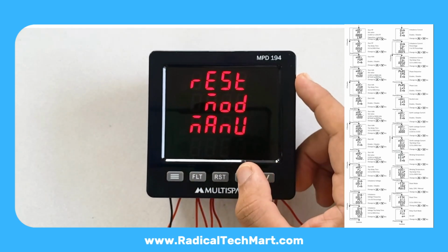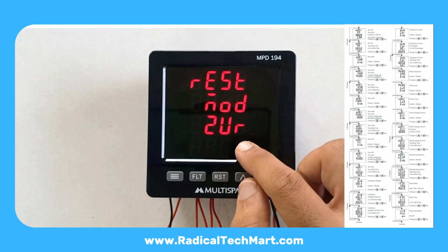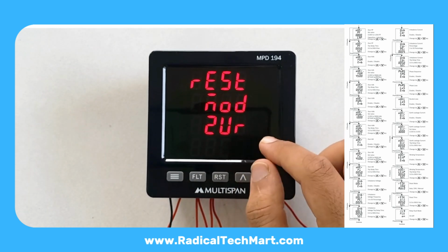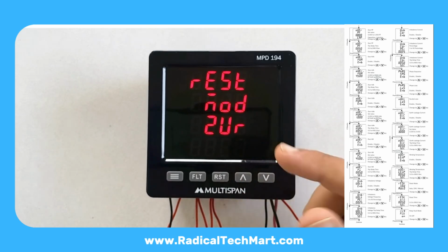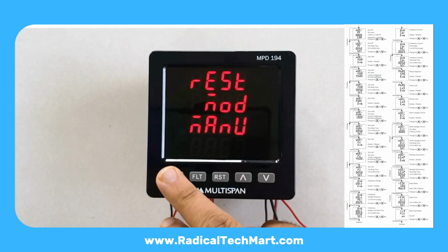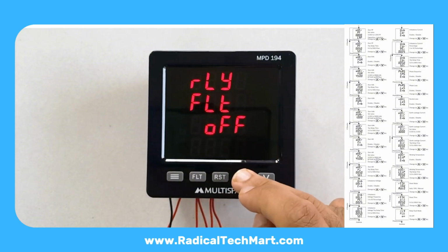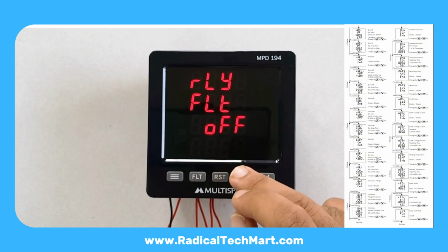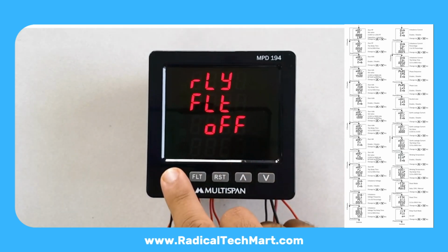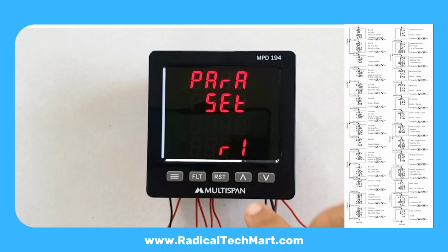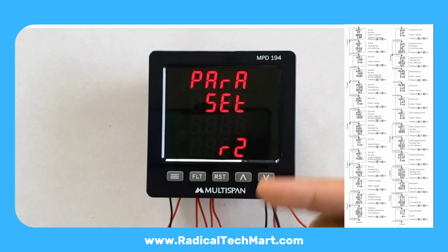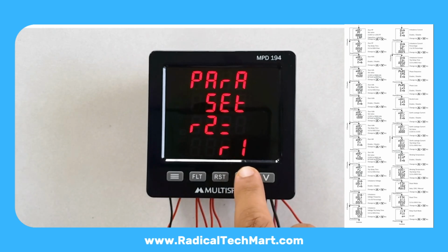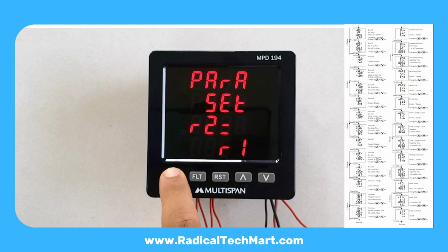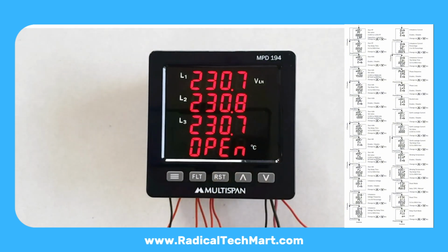At the end, reset mode: Manual, Auto, Zero value reset. In zero value reset mode, when the monitored value returns to 0, the meter auto resets. Relay fault condition: you can select whether the relay should be on or off in fault condition. Failsafe or non-failsafe behavior. For relay 2, you repeat the same steps by selecting R2 at the start. If you select R2 equal to R1, then all settings from relay 1 are copied to relay 2. Press Set to exit back to the main screen.